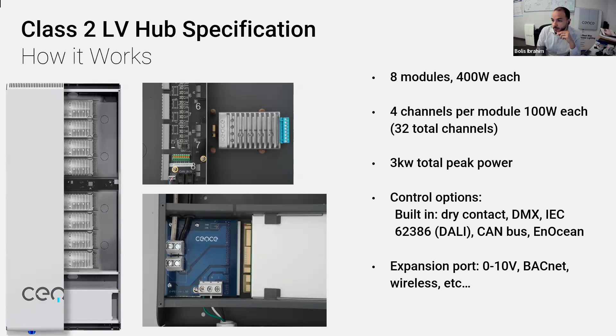And then my favorite, 57.5. Now, 57.5 is a great voltage because it's as close to 60 as you can get while still remaining within the class 2 low voltage limits, providing some headroom. Then it minimizes your voltage drop percentage and allows you to maximize your run length. But it's a good question, these do come in all sorts of shapes and sizes in terms of voltage and current. The remote devices, so PoE had one.